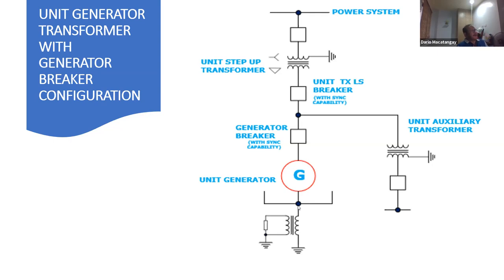So here, one good thing is that, let's say you have a fault on the transformer, okay? When you have a fault in the transformer, this breaker here will open, this breaker here will open, okay? Now, you don't have to open this because the turbine might have a load rejection capability. Now, do you know what load rejection capability is? Load rejection capability is the ability of the turbine to go back to the normal speed after the load is lost. For example, if you have a fault here, before the fault, the generator is powering the grid, right? It's contributing power to the grid.